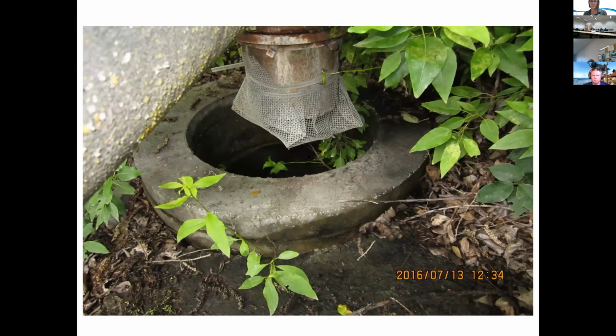The air gap is 2 times the pipe diameter above the overflow rim of the tank. If the pipe is cut at an angle, as you'll see sometimes, it's measured from the lowest point. So 2 times the pipe diameter, measured from the lowest point to the overflow rim. I threw this in there because I don't know if you guys have a bunch of reservoirs, but can you imagine a 4-inch line running full blast? Is this going to stay on there? Yeah, and it's going to clog up. It's going to give you problems later on in life.